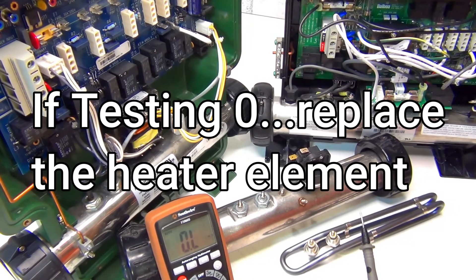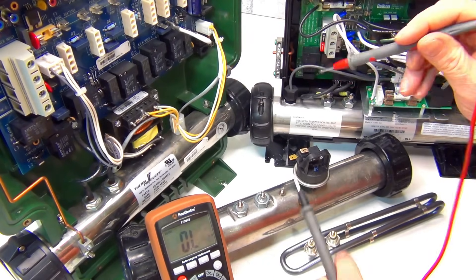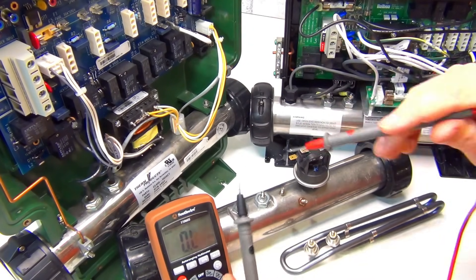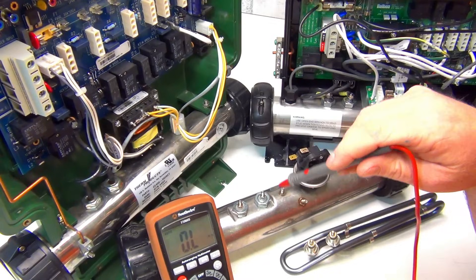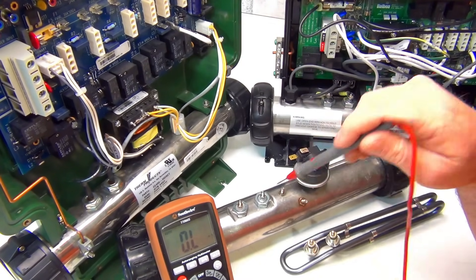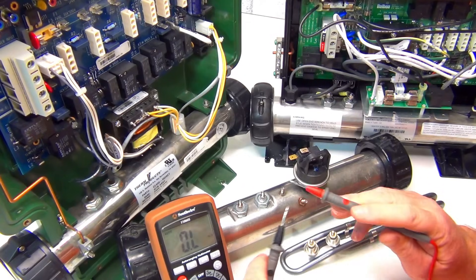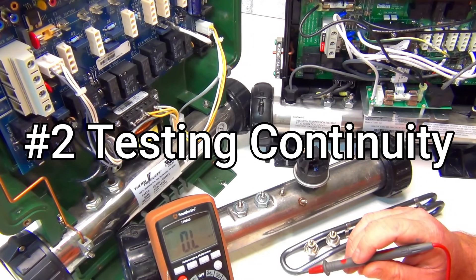I know there's some videos out there that test it and it's zero. Well, if you're testing ohms, you want between 10 and 11 for a hot tub element.